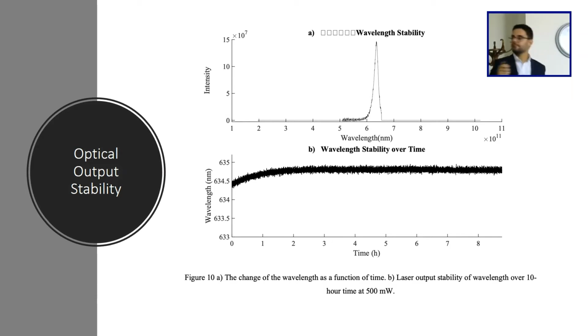And then this is the optical output. No, this is the wavelength stability over 8 hours. You open the system. Just check the scale here. This is very nice, right? Only 0.2, 0.1 nanometer shifted. So we control it quite perfectly. There's about an hour of stabilization. This is not really stabilization, just checking the system, because it's already very close. Plus or minus 3 nanometers is okay. So this system is perfect.